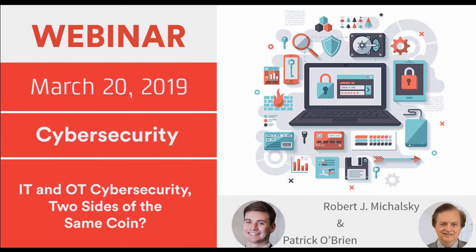And then also in the design phase, documenting the results and how that affects the overall safety system is required. So they're beginning to really tie the idea of safety and cybersecurity more closely together. It's based on the realization that it doesn't matter how reliable a safety system is designed, if it could be easily hacked and compromised, you haven't really achieved that level of safety.